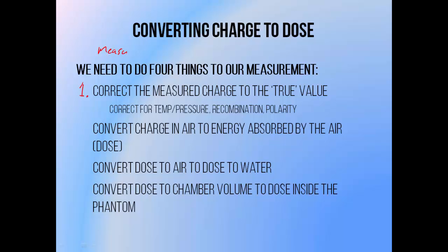This involves accounting for the effects of ambient temperature and pressure, which can affect the amount of air inside the chamber and therefore the amount of energy that it will absorb. Also correcting for recombination, basically accounting for the fact that not all charge generated inside the chamber will be measured. Some of the positive and negative particles will combine and not reach the electrodes to be measured.